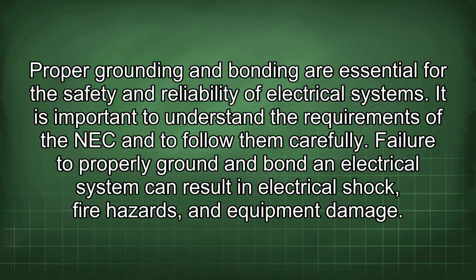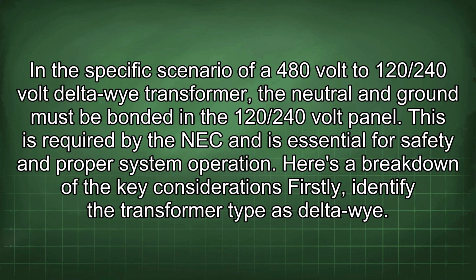It is important to understand the requirements of the NEC and to follow them carefully. Failure to properly ground and bond an electrical system can result in electrical shock, fire hazards, and equipment damage. In the specific scenario of a 480 volt to 120/240 volt delta-wye transformer, the neutral and ground must be bonded in the 120/240 volt panel. This is required by the NEC and is essential for safety and proper system operation.